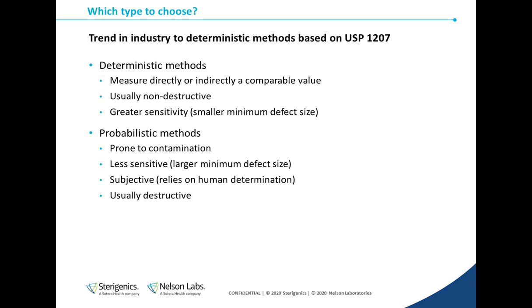Deterministic methods are usually non-destructive, which allows for 100% inline testing during the manufacturing process. And this is especially useful since most typical failure rates in vial and syringe containers are really low and not likely to be detected unless a large number of samples are tested. In a laboratory setting, this means that failing samples can be retested and investigated for failure cause. The smallest detectable defect size is usually smaller with deterministic methods.